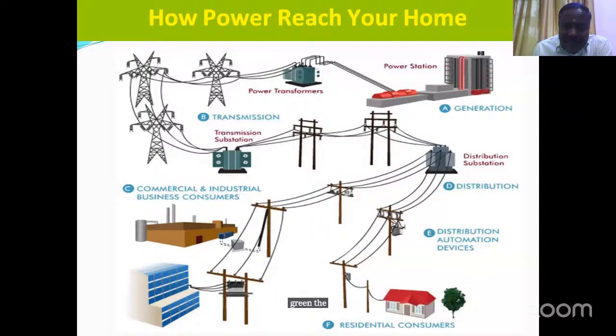The extra high voltage, 220 kV, is transmitted to the load center. At the load center, we again step down the voltage to 110 kV, and again we step it down at our local substations from 110 kV to 11 kV or 22 kV. Then, at these 11 kV and 22 kV lines, we have the distribution transformers. They are located all over our state, in front of our house, in front of our land and everything. That is called a distribution transformer. They have capacities of about 100 kVA, 200 kVA, 250 kVA. And sometimes in towns, we have many 500 kVA distribution transformers. That is a major capacity, 500 kVA.